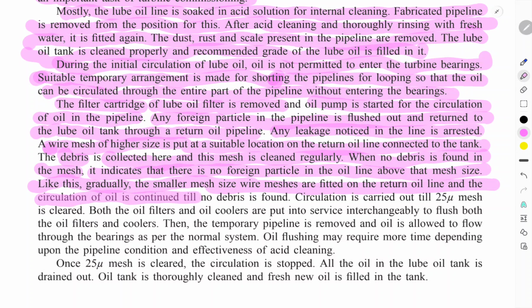The circulation of the oil continues until no debris is found. Circulation is carried out until the 25μ mesh is clean. Both oil filter and oil cooler are put into service interchangeably to flush both the oil filters and coolers. Then the temporary pipeline is removed and the oil is allowed to flow throughout the bearing as per the normal system. The oil flushing may require more time depending upon the pipeline condition and the effectiveness of the acid cleaning.